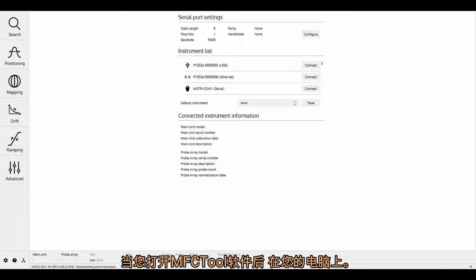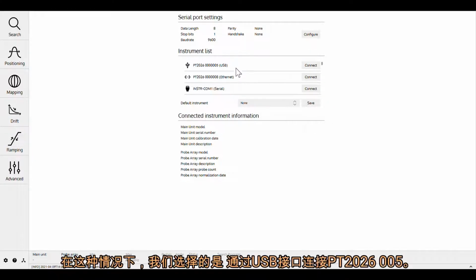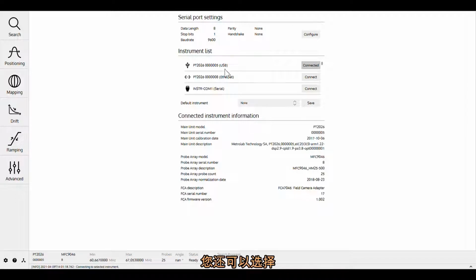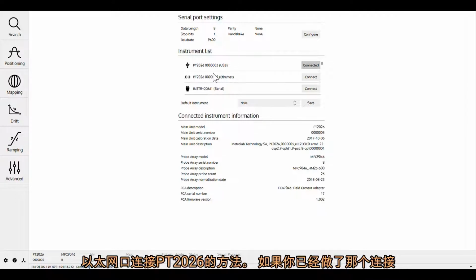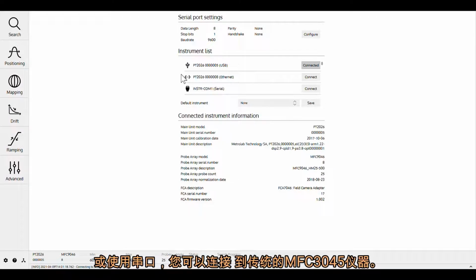Once you have opened the MFCTool software on your computer, you have the possibility to select the instrument that you will be working with. In this case, we are selecting the PT2026-05 connected via the USB port. You would also have the choice of connecting a PT2026 on Ethernet port if you've done that connection, or using serial port you can connect to legacy MFC3045 instruments.